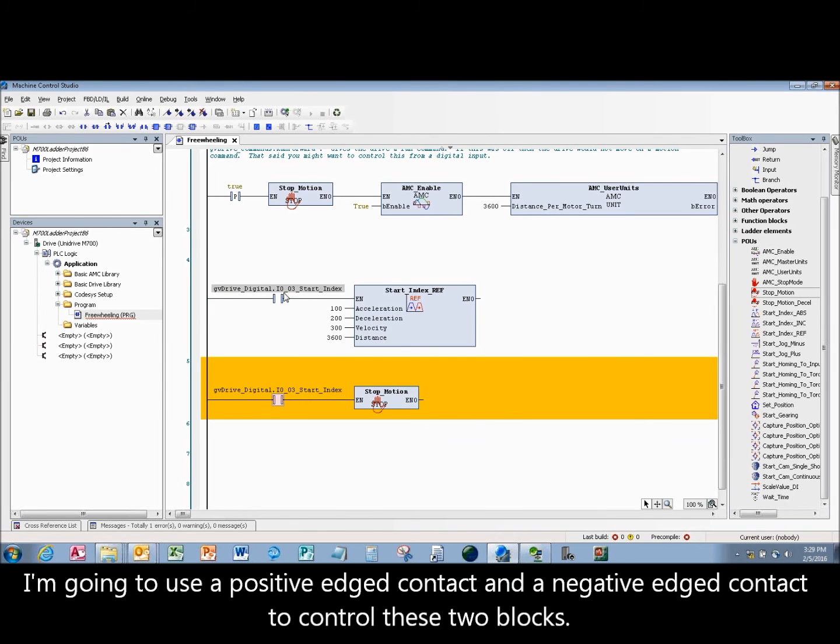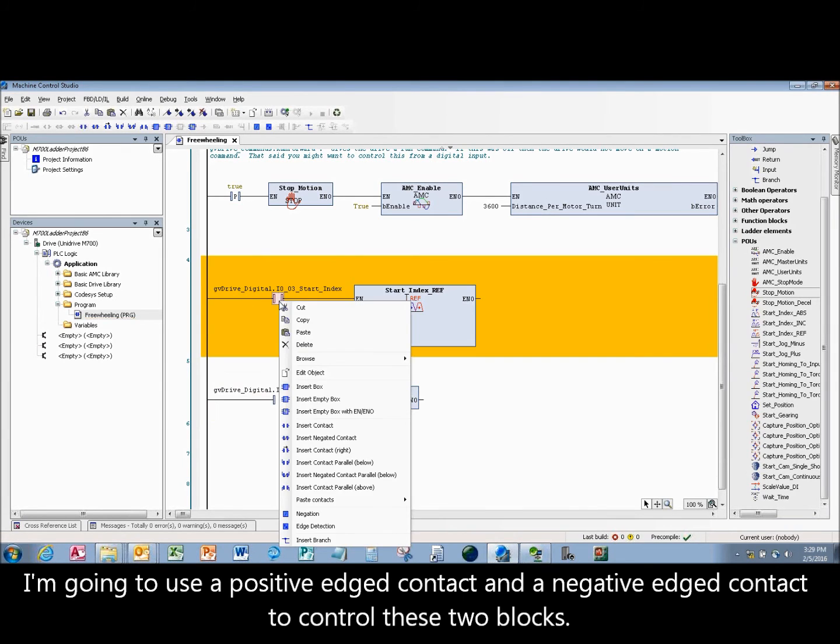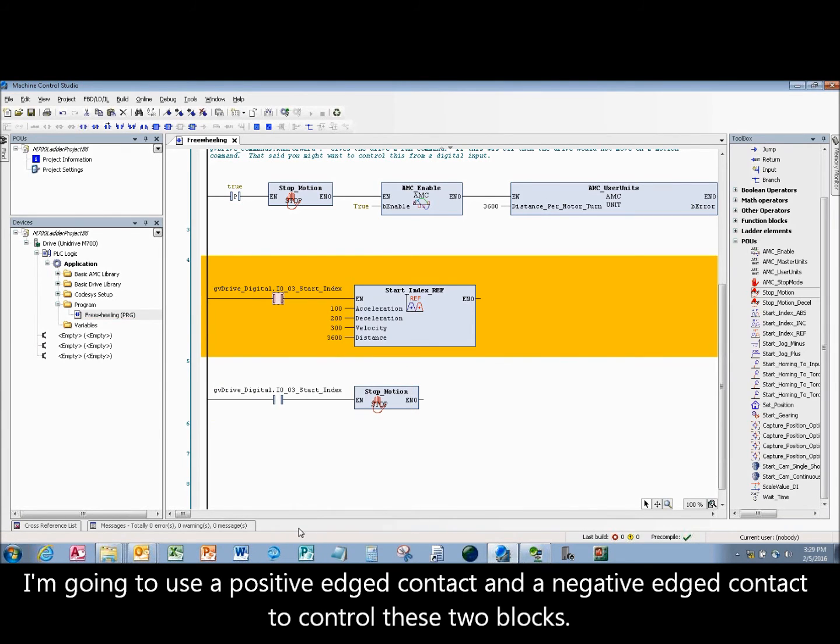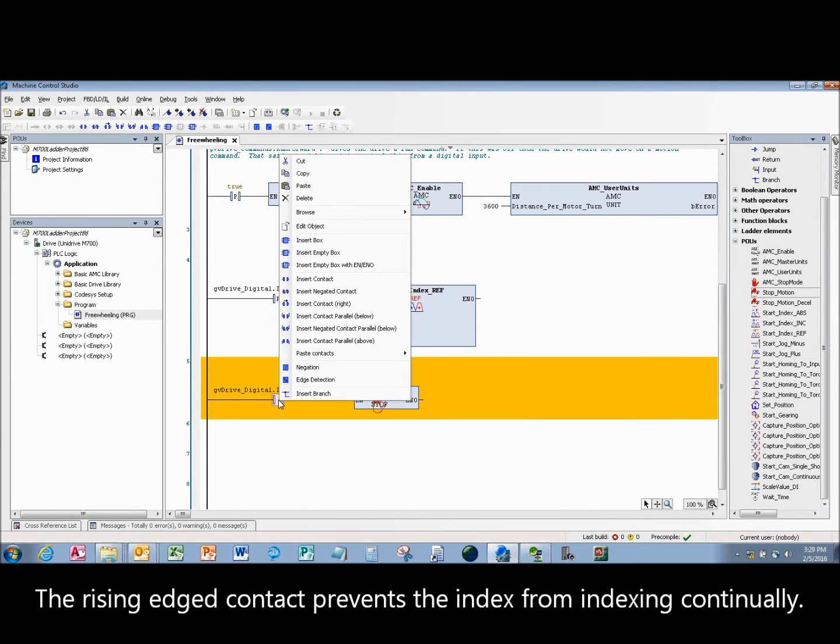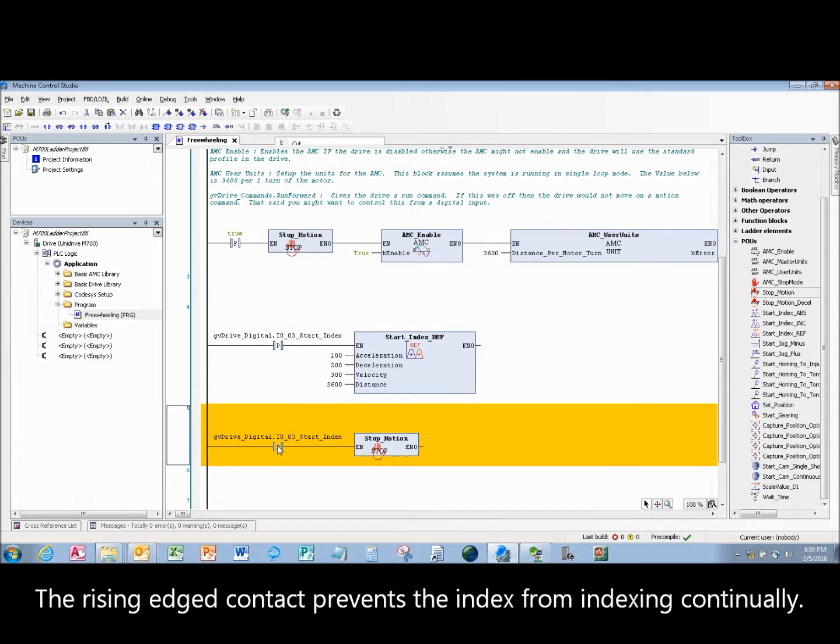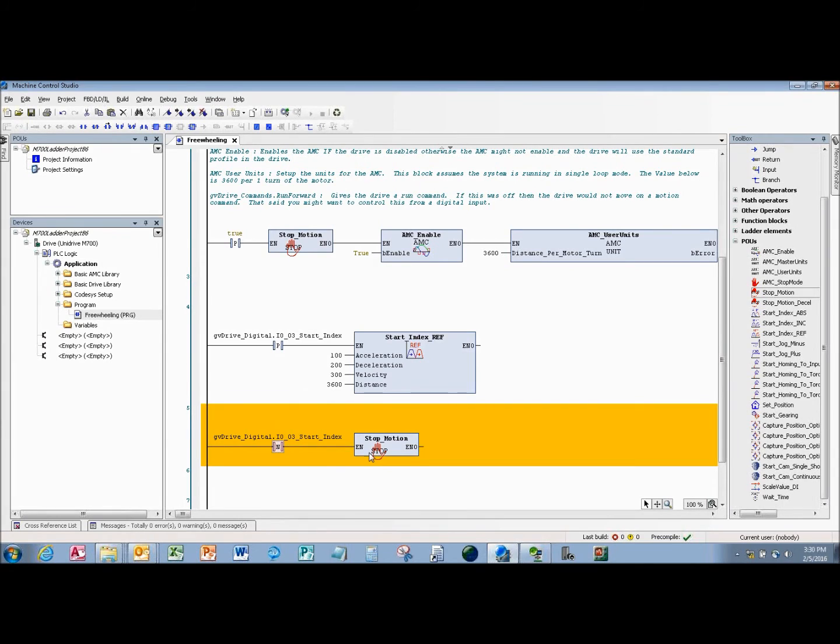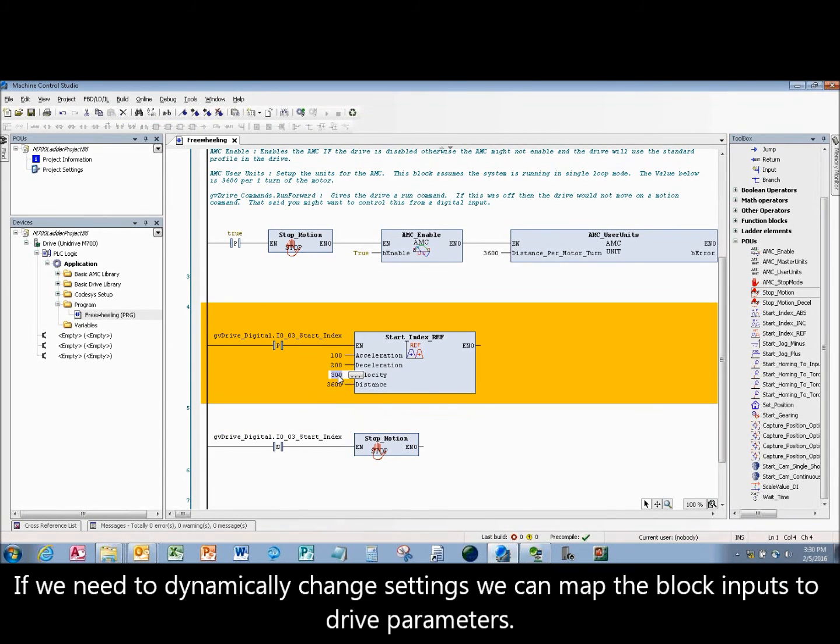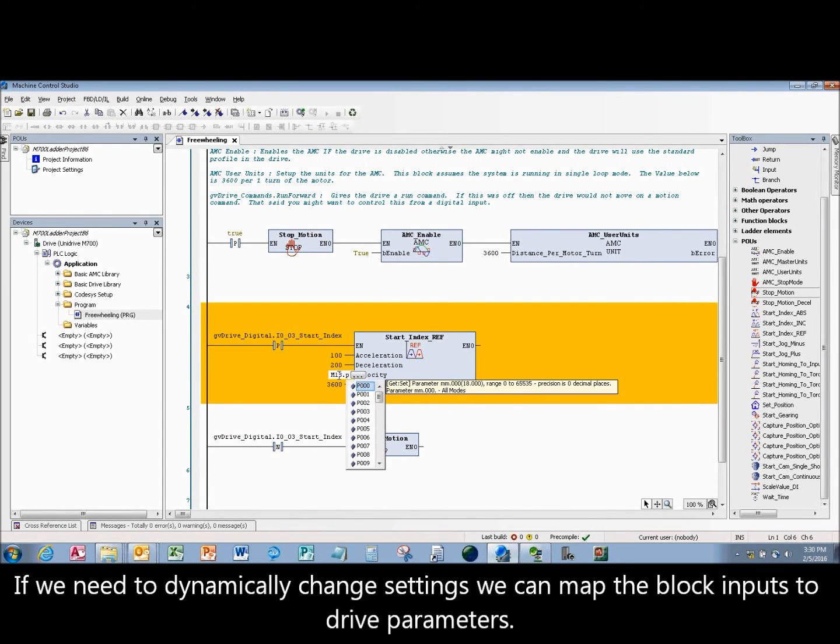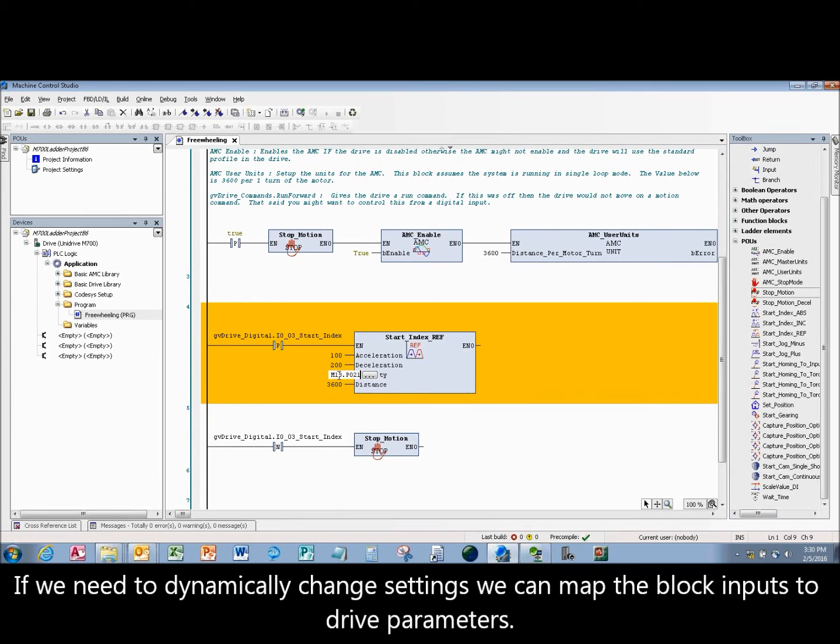I'm going to use a positive edge contact and a negative edge contact to control these two blocks. The rising edge contact prevents the index from indexing continually. If we need to dynamically change settings we can map the block inputs to drive parameters.